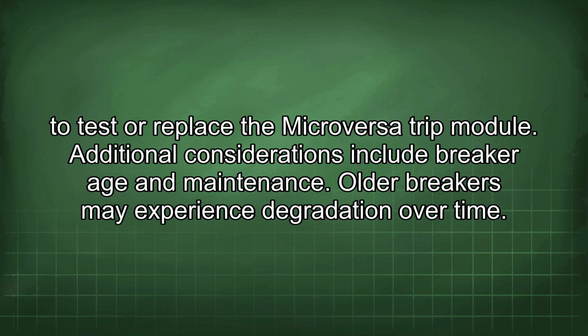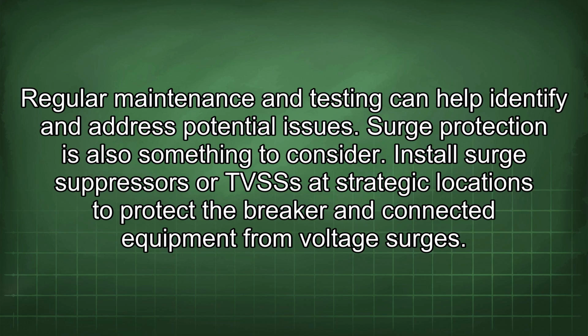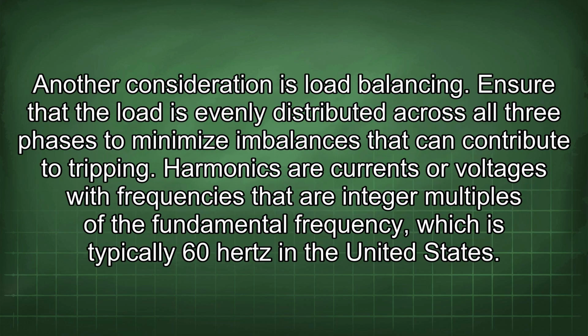Additional considerations include breaker age and maintenance. Older breakers may experience degradation over time. Regular maintenance and testing can help identify and address potential issues. Surge protection is also something to consider. Install surge suppressors or TVSSs at strategic locations to protect the breaker and connected equipment from voltage surges. Another consideration is load balancing. Ensure that the load is evenly distributed across all 3 phases to minimize imbalances that can contribute to tripping.